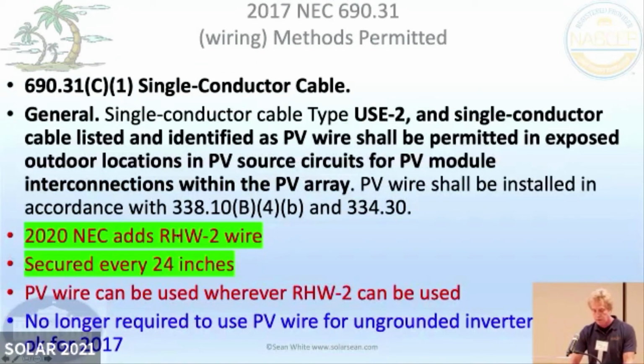Another thing that was new: we've always used USE2 wire, that UV rated wire that's underneath the PV arrays. It's really common. You could also use PV wire, but in 2020 NEC, it has to be dual listed also as RHW-2. But if you went shopping, you could find out that all that USE2 wire you've been installing is already RHW-2 listed.